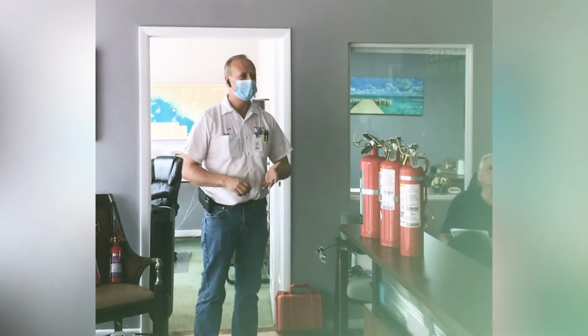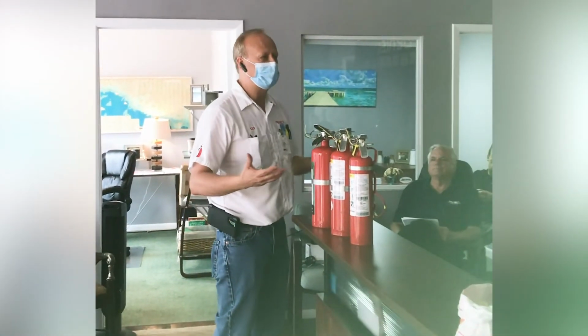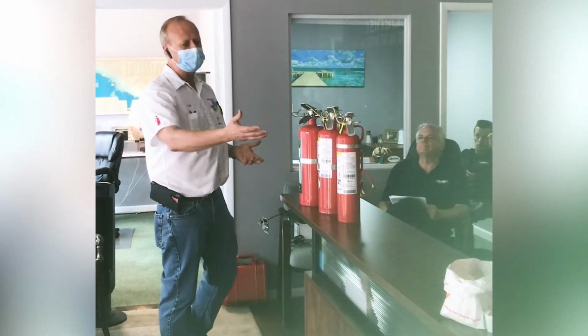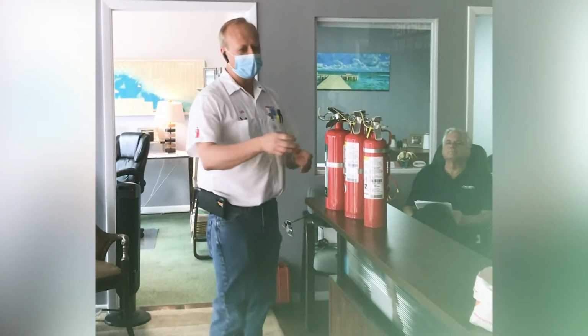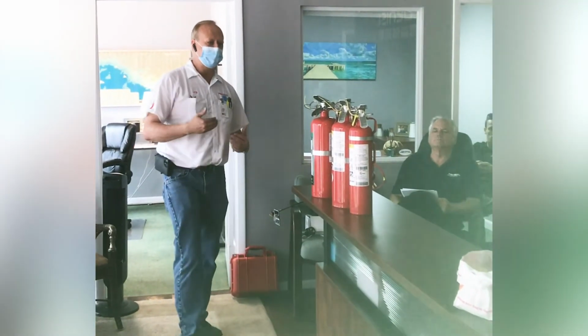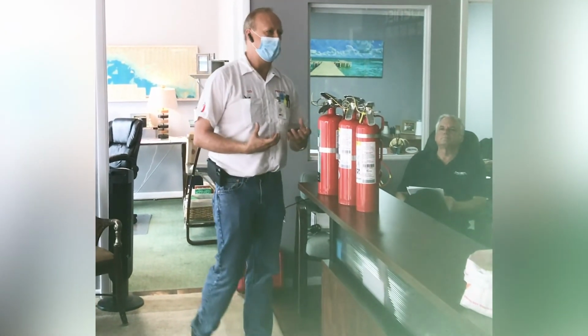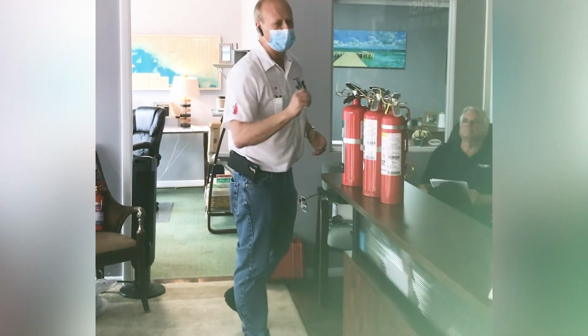Where do you use those? I mean, if they're that abrasive. Because it's cheap and cheerful, okay. Nobody wants to pay to get ABC to cover this office is $800 a fire extinguisher. Oh. This fire extinguisher costs $79.95. Mm. So it's 10 times more money to get the coverage that you need, because this gas, you need a lot of it to get to A rating. I got you. To get paper, wood, and trash. Yeah, you've gotta have a lot, and it's very expensive.